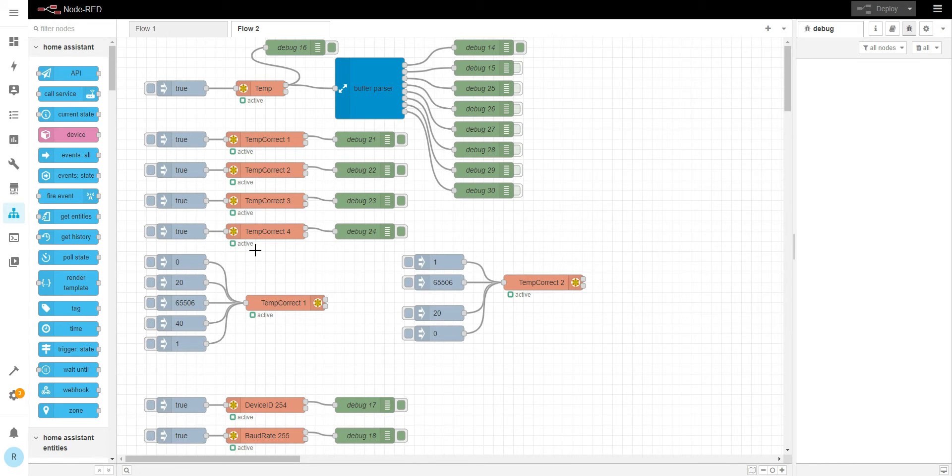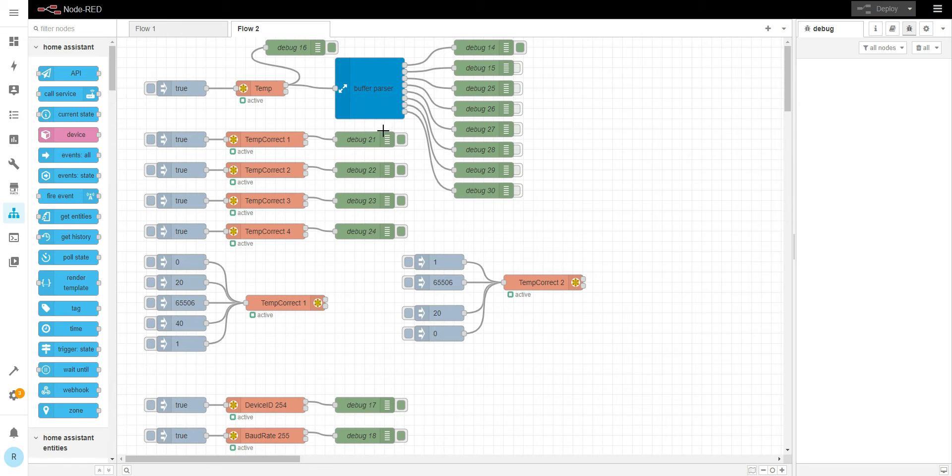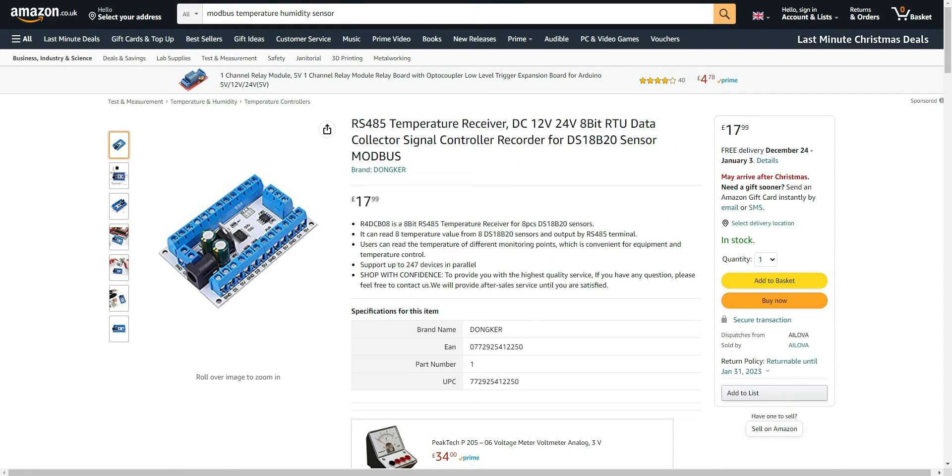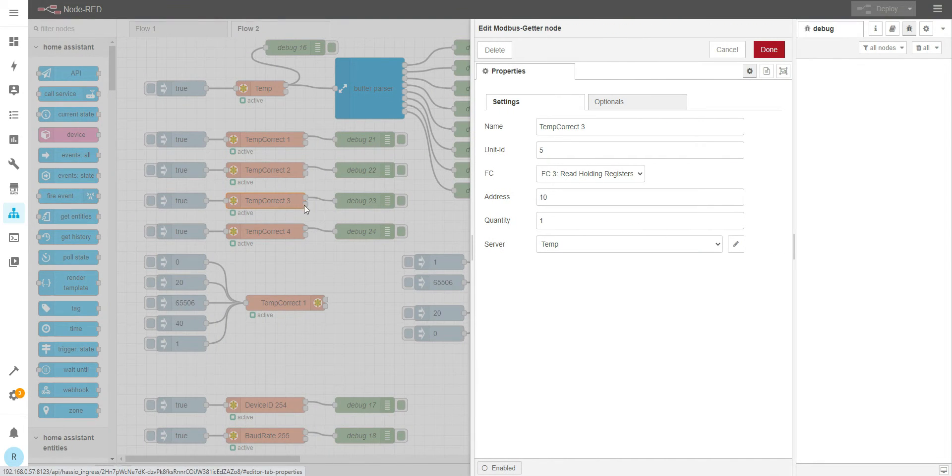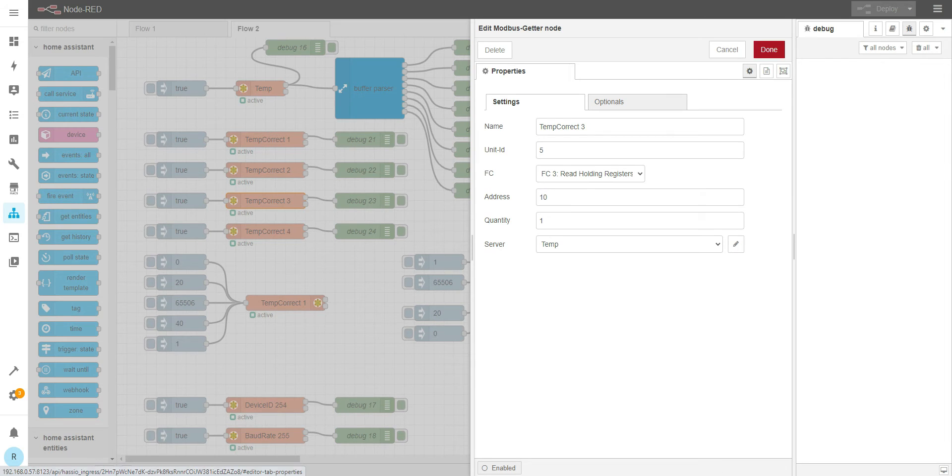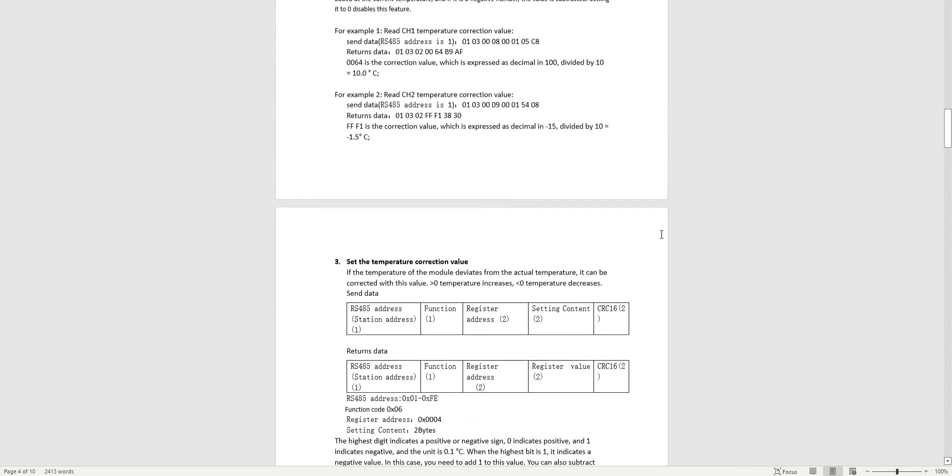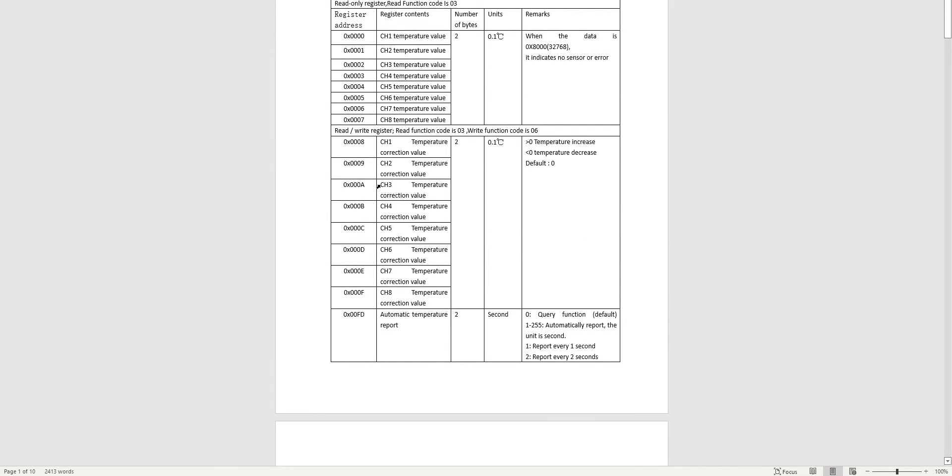I almost forgot one quite important thing. This is the unit. So temperature correction is address number 10, but when we go to the Modbus map we got this kind of address. First channel is number 8, second number 9, third number A, fourth number B, fifth number C. So what's that mean? That means it's a hex address.